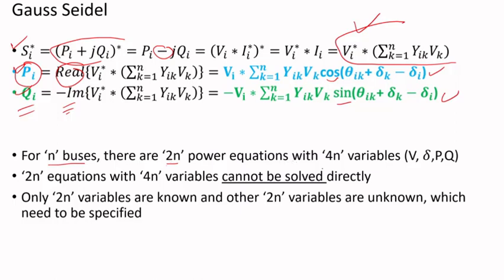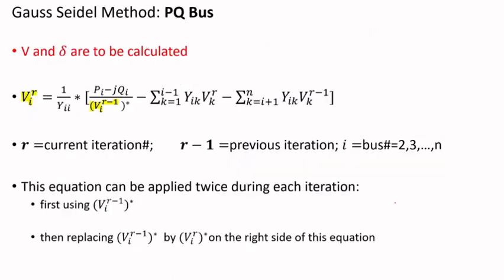If you have n buses there will be 2n power equations with 4n variables — voltage, angle, P, and Q. At each bus, only two of those four variables are known, so two n variables are known and two n are unknown. This system cannot be solved directly.